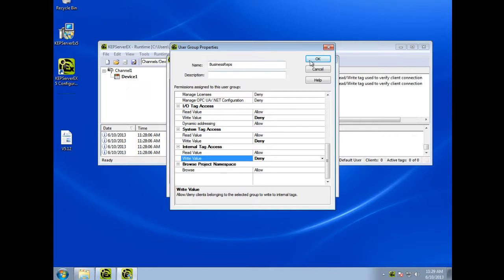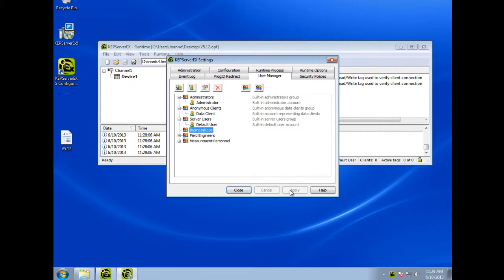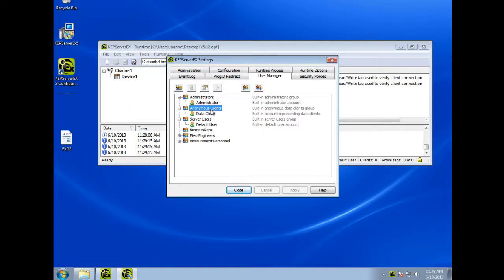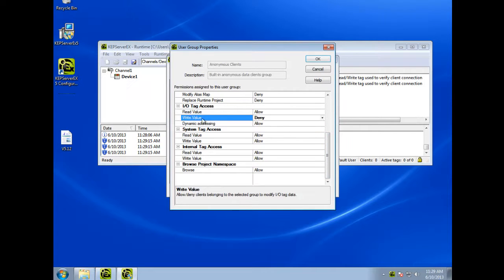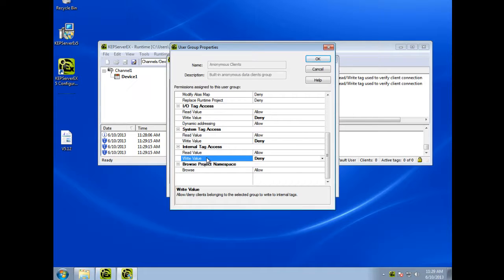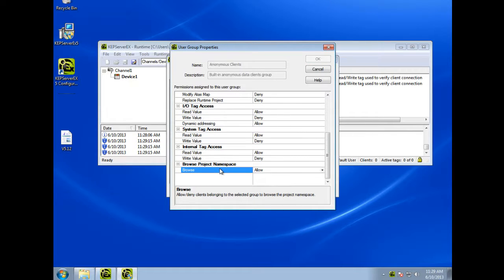The server administrator can apply global permissions to control data access for all anonymous clients like OPC DA and native interfaces. For example, you may want to restrict everyone to read-only access, as shown by denying write privileges with the business reps group previously. Apply other permissions such as browsing privileges as determined by your project needs.